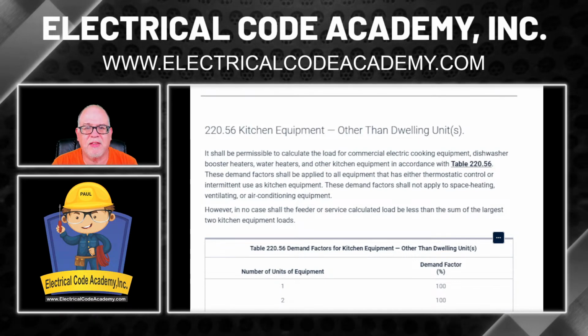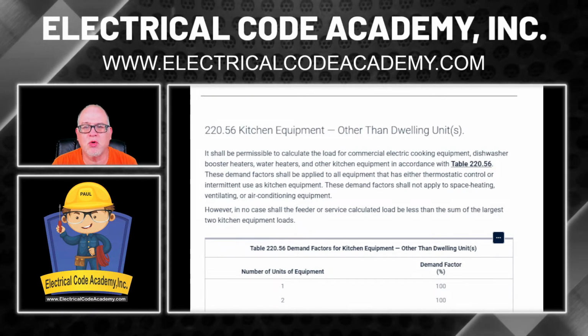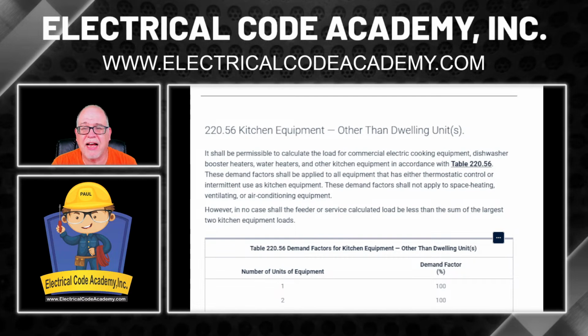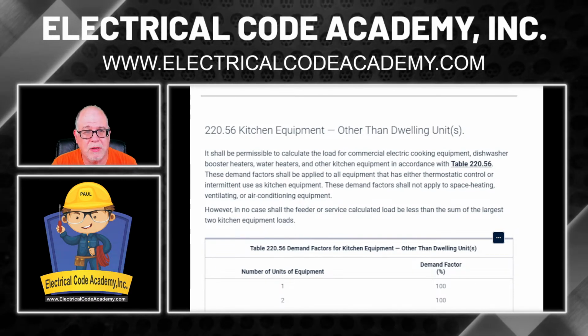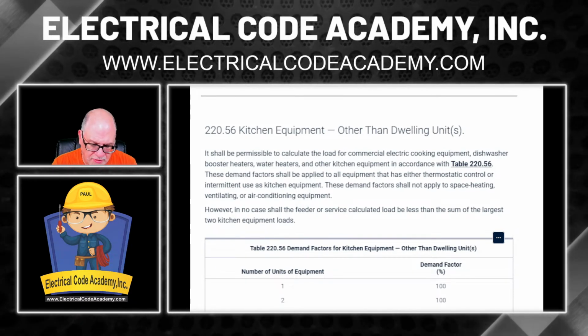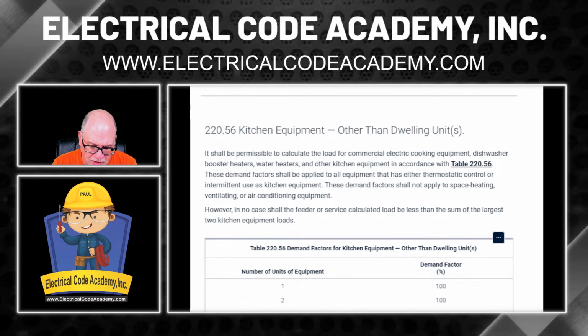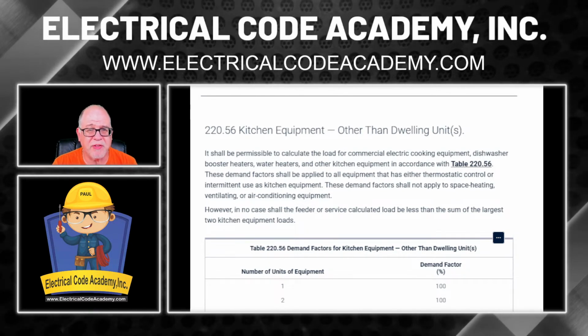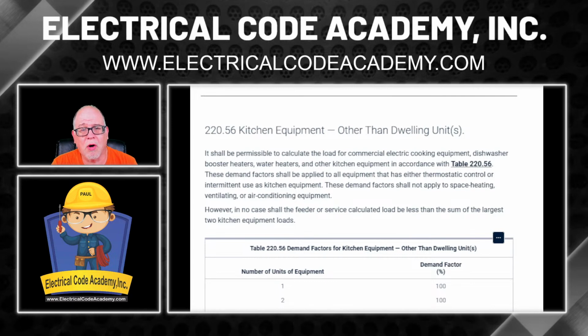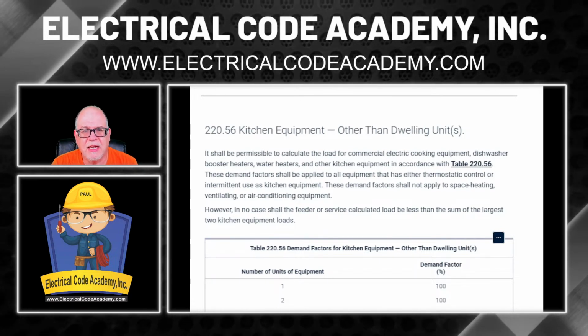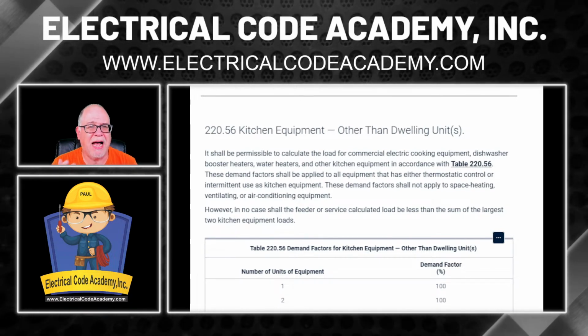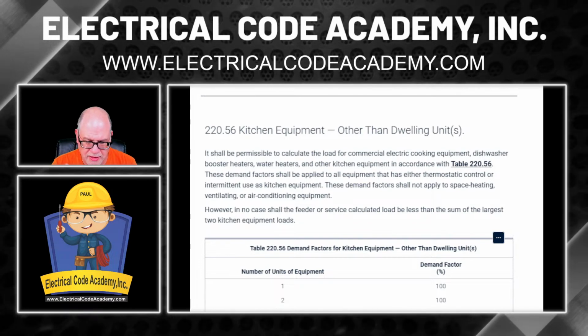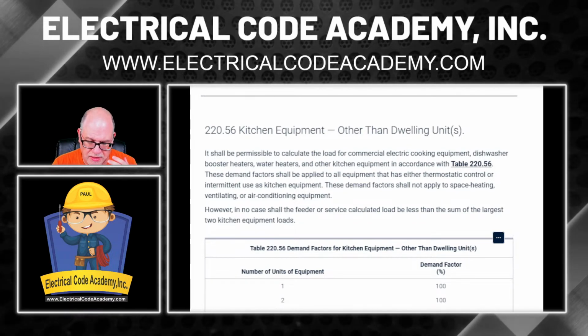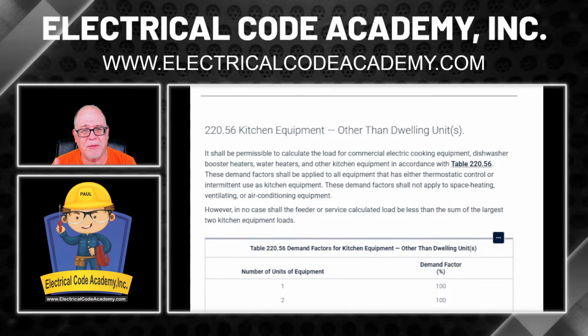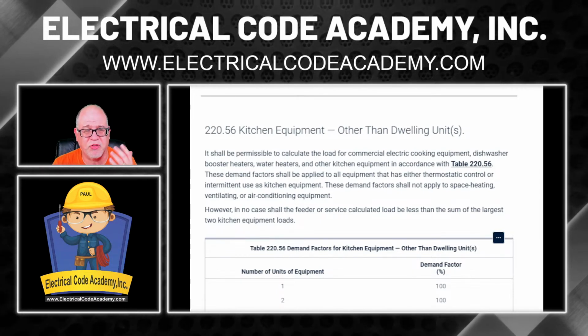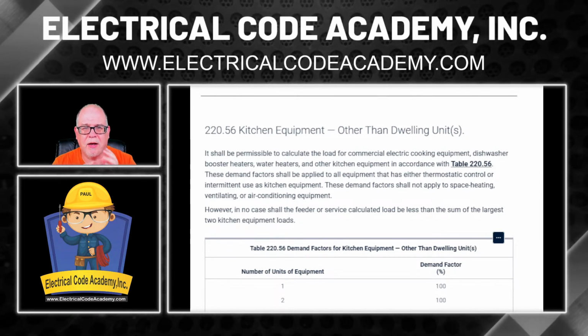It also says these demand factors shall be applied to all equipment that has either thermostatic control, and most of this stuff, the ovens, the grills, the deep fryers, and all that kind of stuff, are going to be thermostatic controlled. It says, or intermittent use as kitchen equipment. Well, obviously, the disposal's on when you need it. The water heater is going to come on when it's needed. The booster heater is going to come on when it's needed, but that's also probably thermostatically controlled.